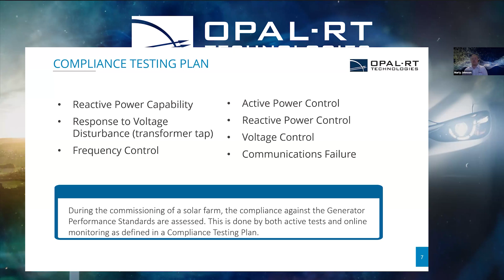In the hardware in the loop, there are a few things we can do that we don't get to do during on-site commissioning, which give us better confidence about the control system design. Firstly, we can replay network events. One particular event in Australia was the Callide event, where a large generator effectively blew up and resulted in a large frequency deviation. We can replay these events through the actual controllers and hardware to see how they respond. We can apply faults and make sure the actual equipment, especially if we're doing inverter controller testing, works correctly as we've modeled.